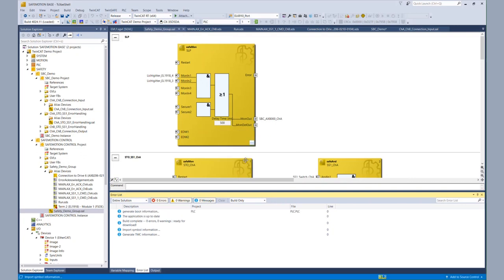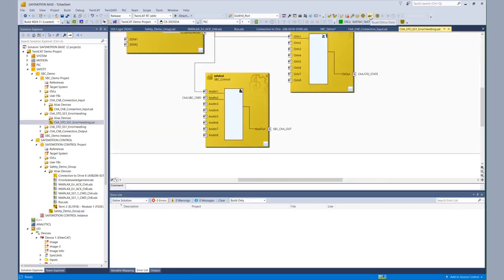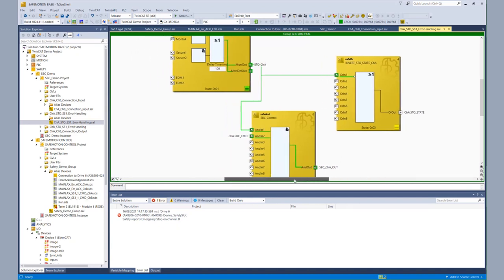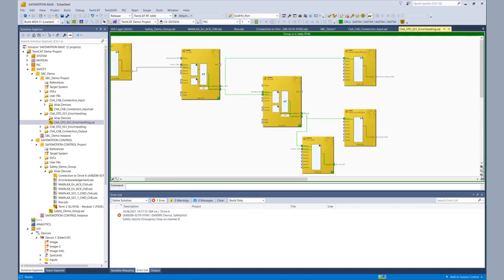After that we can start to examine if our SBC is working. We are now controlling the EL6910 SBC signal, transferring it to the AX8000, and within the AX8000 error handling we are combining it with STO. So we go to the online view of the channel A error handling. We see that the STO signal is present, the SBC command and the SBC channel A out signal is present. And if everything was assigned correctly, we have a brake release from the TwinSafe side and we can try to run the motor from the functional side.